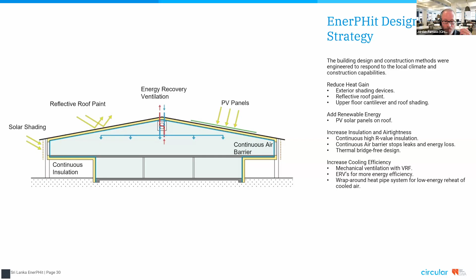For cooling and dehumidification, Dylan already went through the magic of the wraparound heat pipe for dehumidification. We were using a VRF system for cooling, and the energy recovery ventilation means we're able to bring in lots of fresh air while maintaining around 90% efficiency - so the cool air leaving the building transfers its cooling at a very high level to the warmer incoming fresh air.